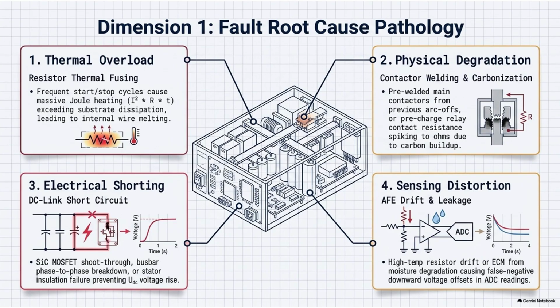And these silicon switches can fail in a very specific way, according to the document. They switch thousands of times per second. If an IGBT gets hit with a voltage spike or thermal stress, the delicate crystalline structure of the silicon can break down. It suffers a shoot-through failure, meaning the semiconductor melts internally and forms a permanent, uncontrolled pathway straight to the ground. It becomes a dead short.